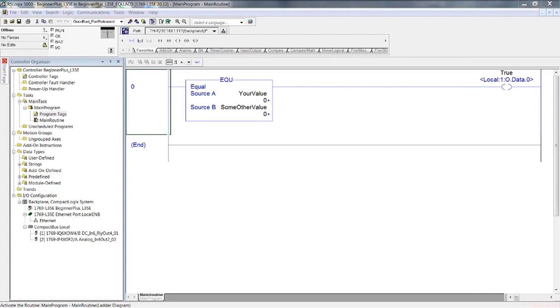In the most fundamental terms, the XIC — true-if-on — and the XIO — true-if-off — are comparison instructions. They are the binary equivalent to the equal instruction, the EQU. The XIC would be true if the bit memory it addresses is equal to one; the XIO would be true if the bit memory it addresses is equal to zero. It is unnecessary to understand the depths of the instruction set to be a successful PLC-PAC programmer. However, a cognizance of the instructions at a binary level will serve you well when troubleshooting and when writing simplistic, readable code.